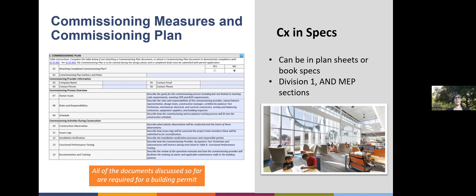There's a template about what needs to be included. So all of those things -- OPR, BOD, commissioning, the design review, the measures, the commissioning plan -- all packaged up, that should be part of your building permit. That's the permit, should all be done ahead of time. In the old days, we used to bring on a commissioning authority during construction. Now all of that has to be done during design and permitting.